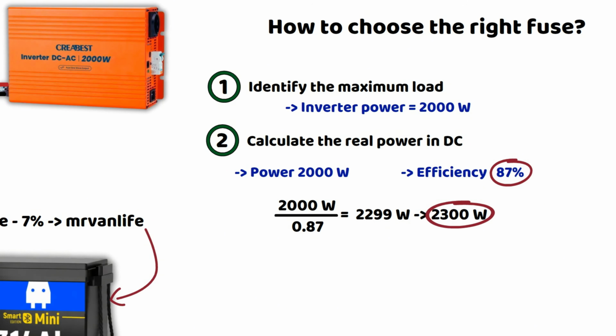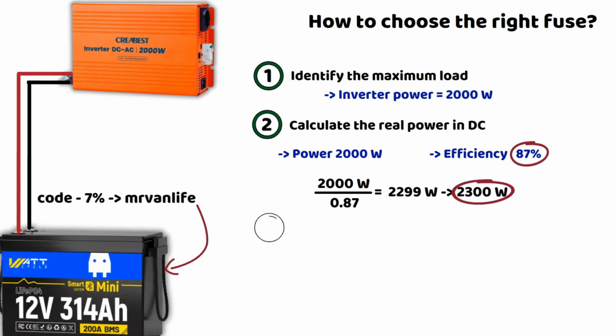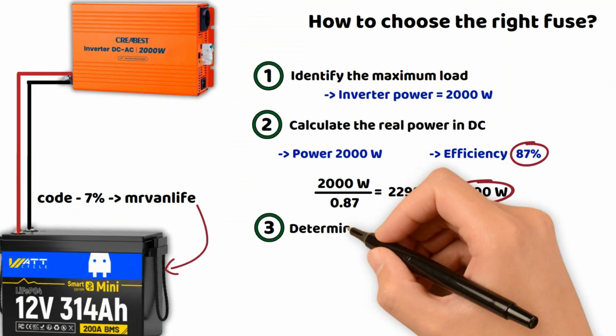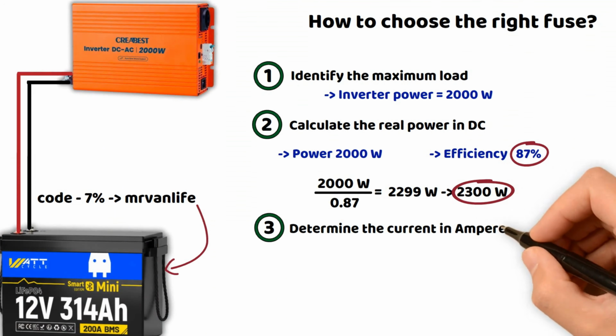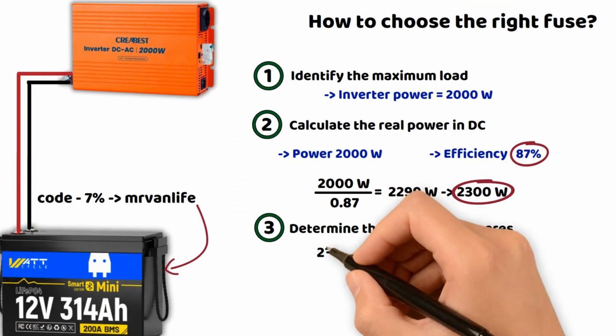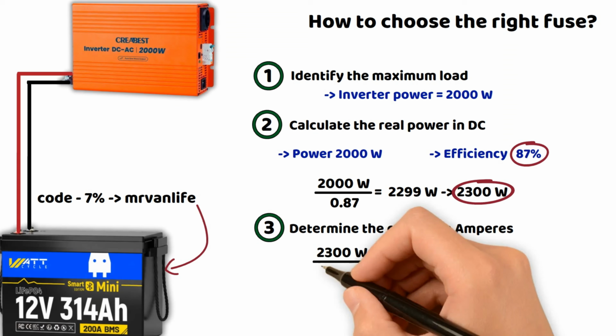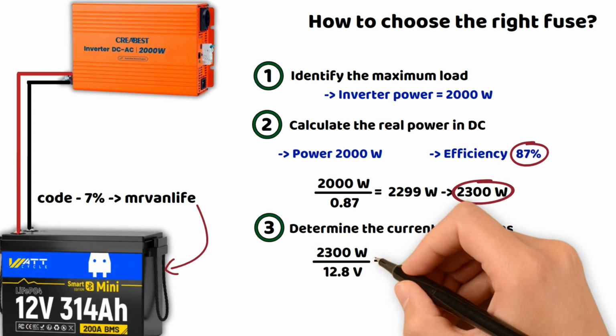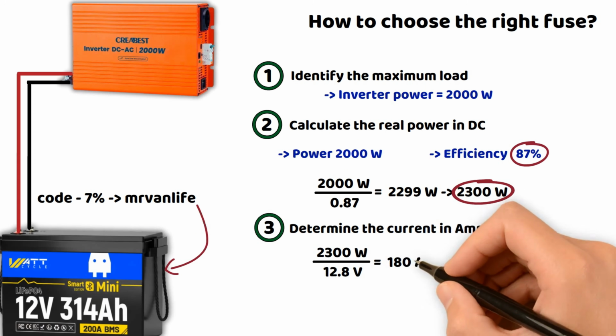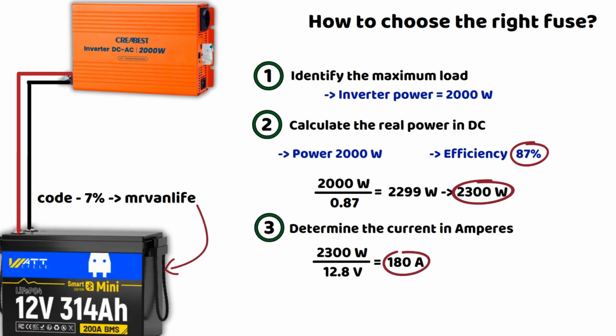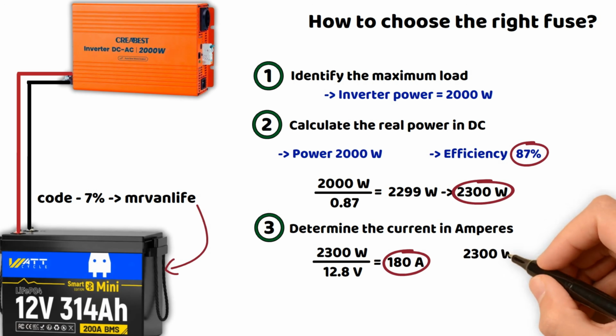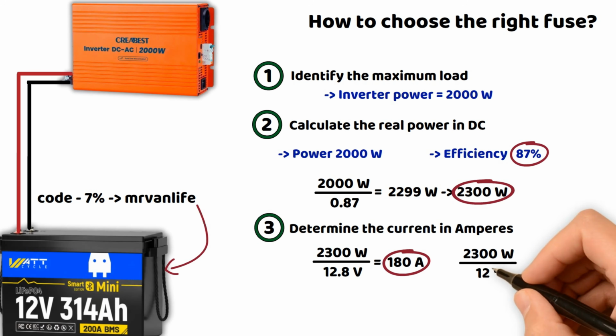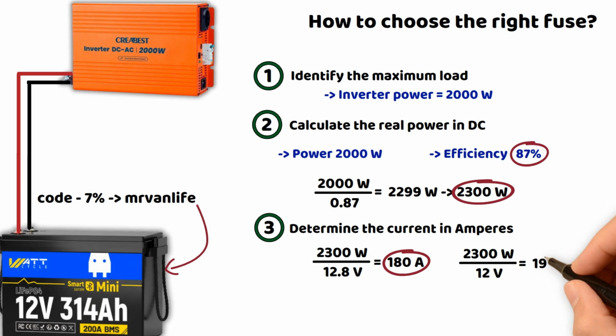Step 3. Determine the current in amperes. For that, it's simple. We divide this power of 2300 watts by the battery voltage. That gives us 180 amperes, rounding off. 2300 watts divided by 12.8 equals 180 amperes. But we could also just use 12 volts because in practice it's quite possible that we'll drop below 12.8. So 2300 divided by 12 equals precisely 191.6 amperes.